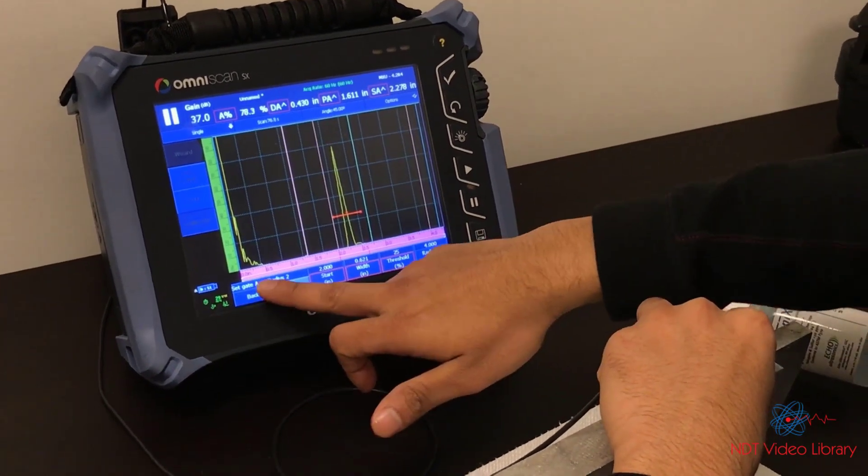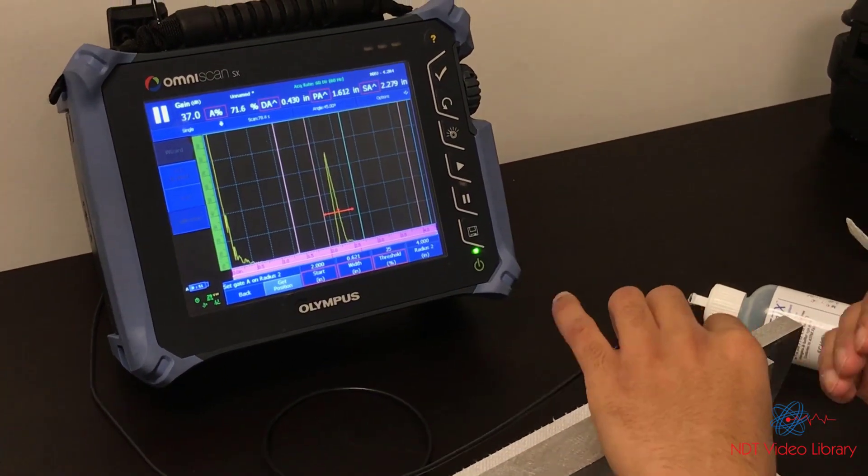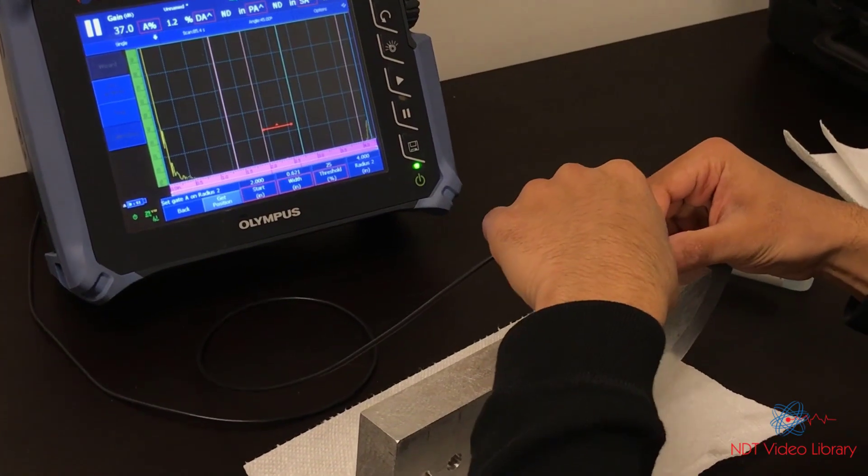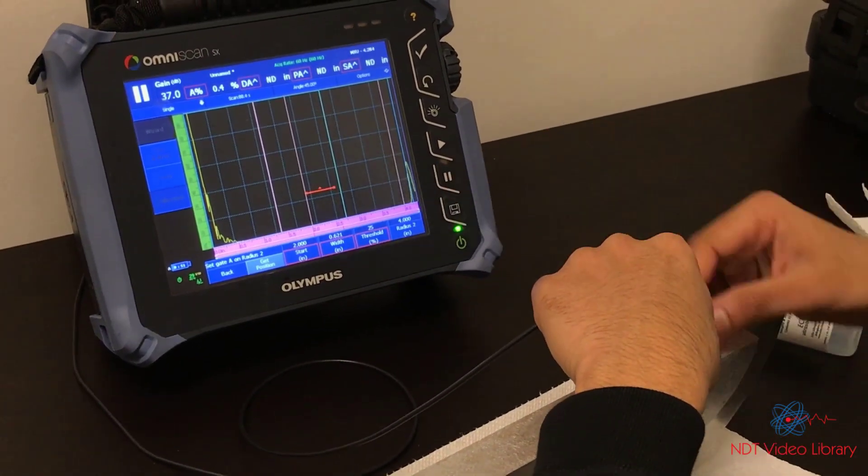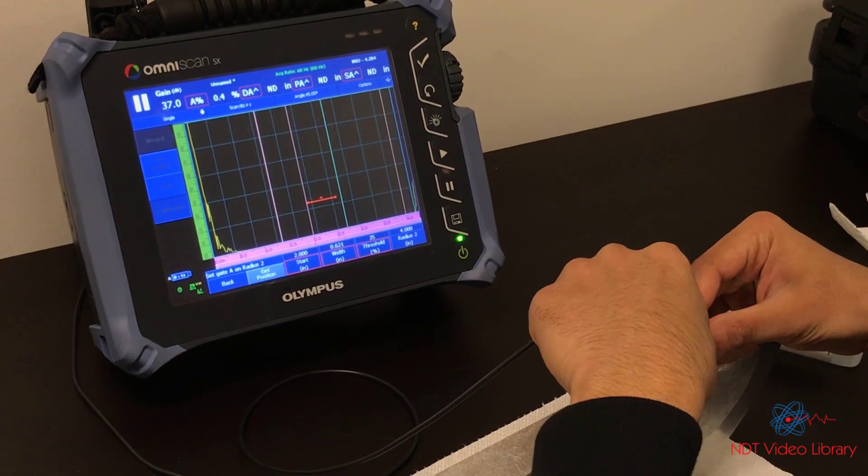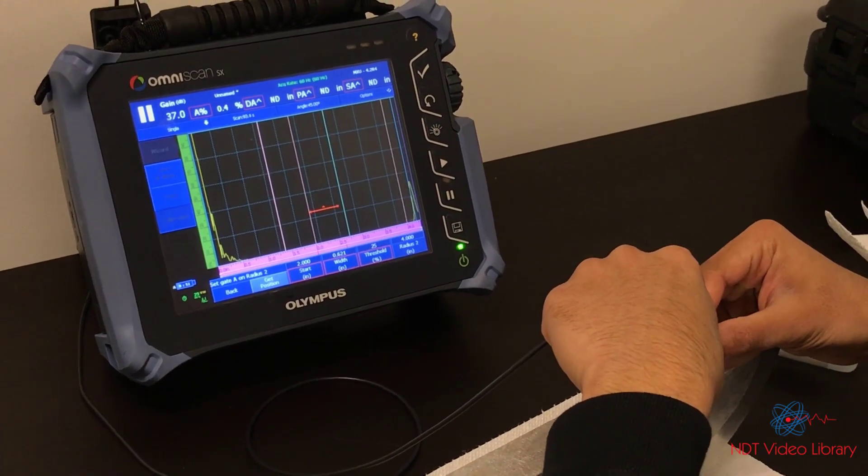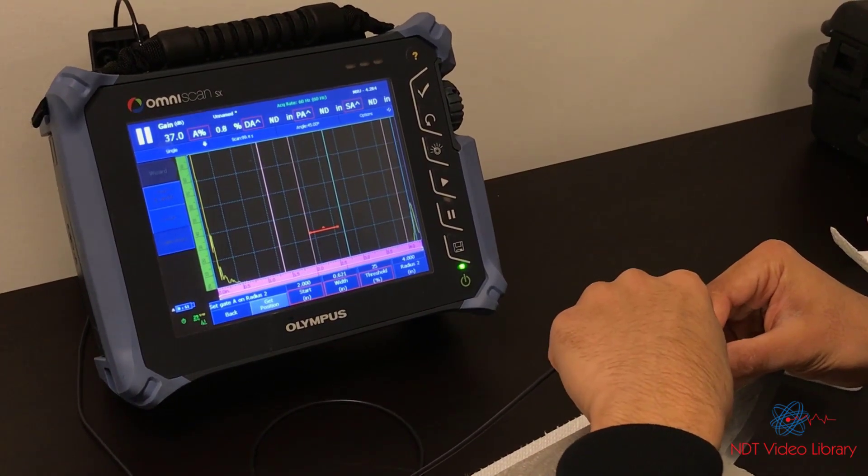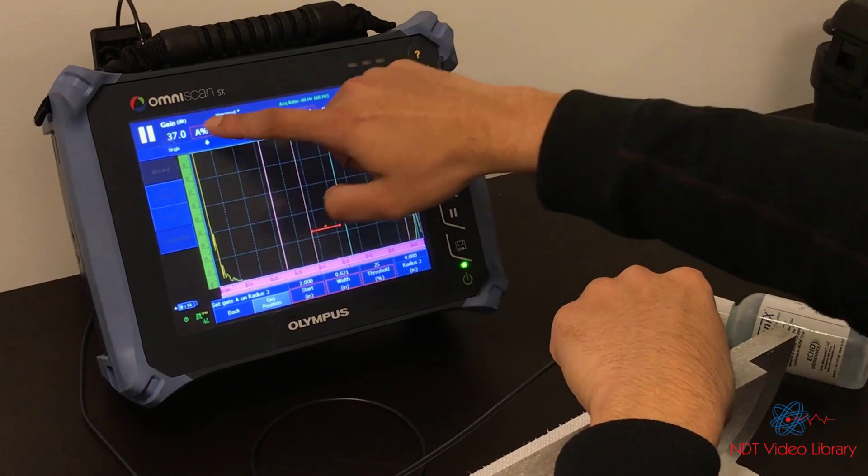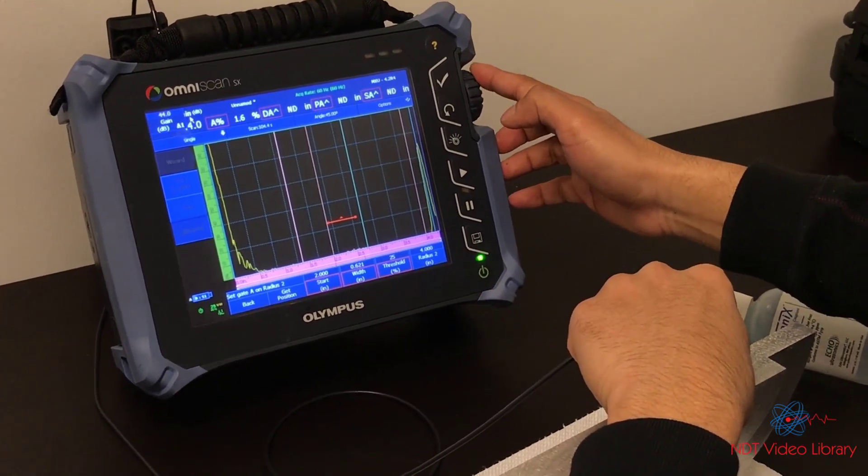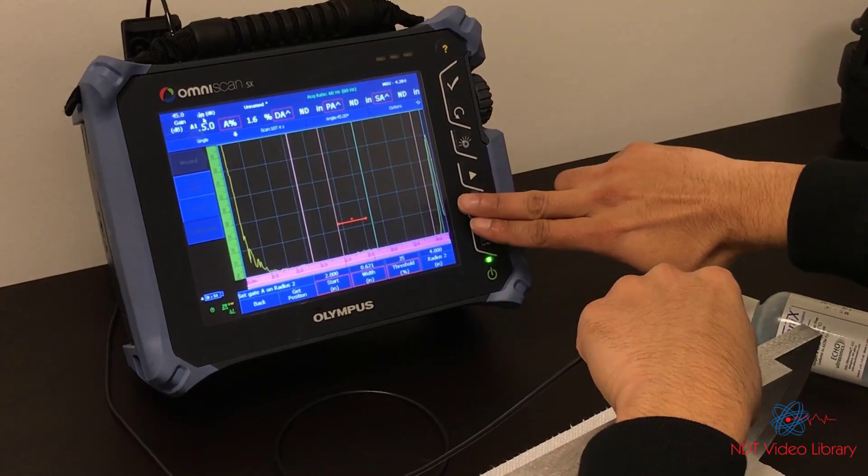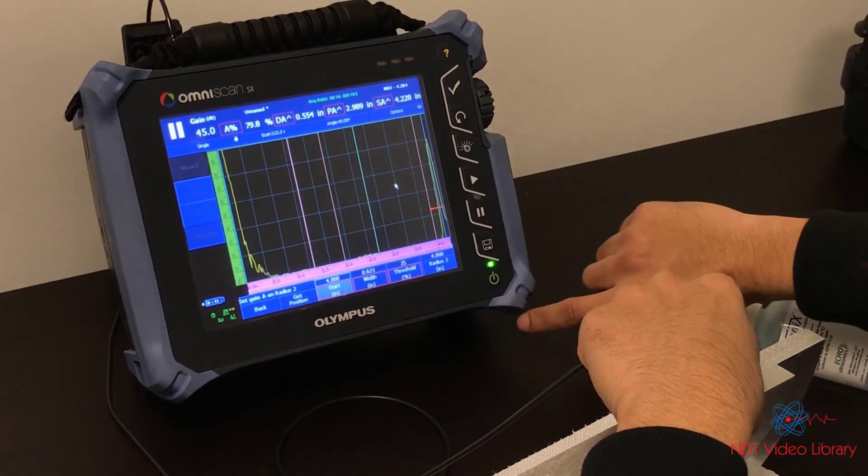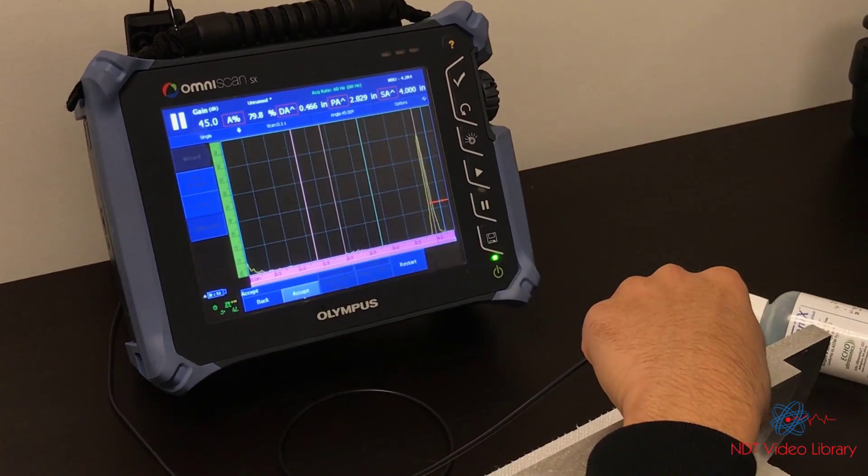Now it says set gate A on radius 2. Radius 2 is just the radius on the other side, which is 4 inch. You see that signal all the way at the end. That's your 4 inch signal. Try to maximize it. Right there. And then increase the decibels to 80%. To get position, move the gate on that signal and get position. That's it.